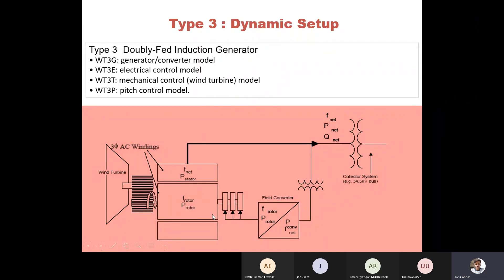Type 3 is the doubly-fed induction generator (DFIG). It is an induction generator with feedback from the output at the POI, using a field converter feeding back to the rotor. The dynamic models involved are the generator/converter model, electrical control model, mechanical control model, and pitch control model. The converter control is included in the electrical control model. The DFIG is efficiency-wise a good machine with advanced control, and reactive power is not an issue — voltage can be maintained easily. However, in all three types the generators are coupled to the grid, so any grid fault affects their performance.